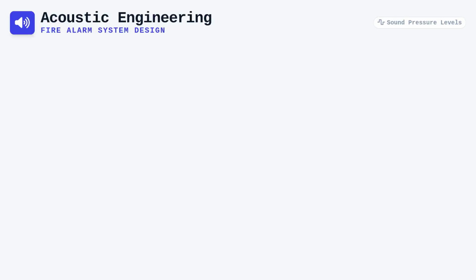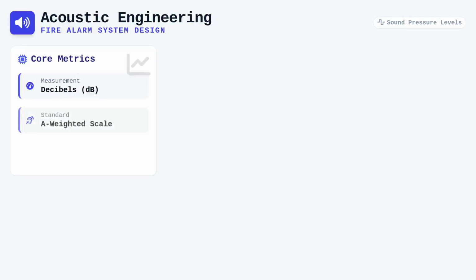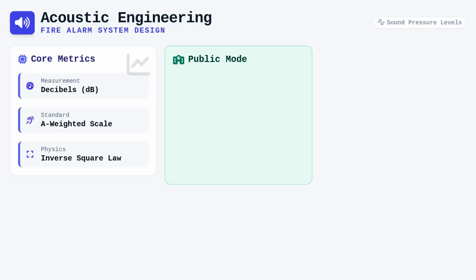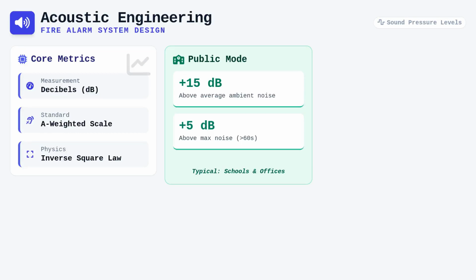Acoustic engineering within fire alarm systems requires a solid grasp of sound pressure levels and ambient noise environments. We measure sound in decibels, often utilizing the A-weighted scale to reflect human hearing sensitivity, which is why we must ensure our alarms provide a specific decibel surplus above the prevailing ambient noise level. In public mode, such as in schools or offices, that surplus is typically 15 decibels over the average ambient sound or 5 decibels over the maximum sound that lasts longer than 60 seconds.